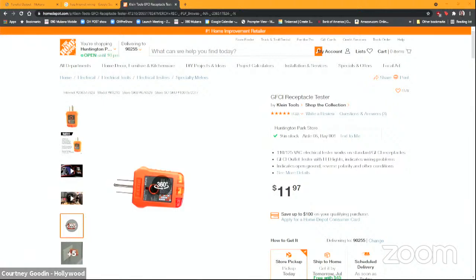But the main thing is if the 3 little lights light up correctly, you know that it's got a good ground, and neutral and hot are not reversed. The best way to blow up equipment or electrocute somebody is to plug into an outlet that some bozo has hooked up himself because he fancies himself a do-it-yourselfer, and has reversed the neutral and ground to the socket. This will detect that kind of stuff. You can electrocute yourself if you come across faulty grounds.